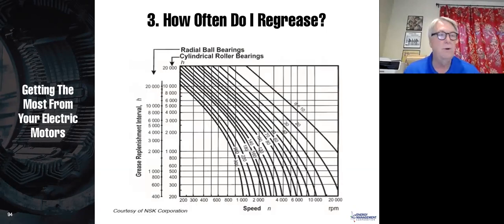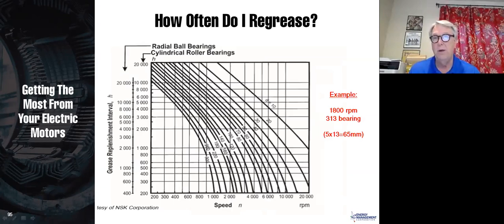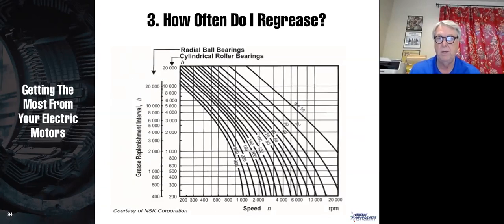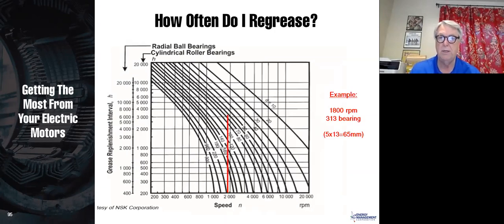How often do you re-grease? This is number 3. This is a much better way to go, and it's included in the booklet that is included with this class. So I'm just including a couple of curves. And so over here, you look at, do you have a radial ball bearing or a cylindrical roller bearing? There we go. We've got some red lines that'll help you out there. So first of all, I look at my speed on the bottom. Let's say I got an 1800 RPM motor.